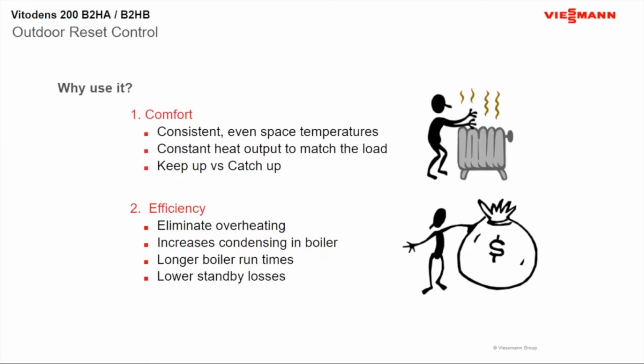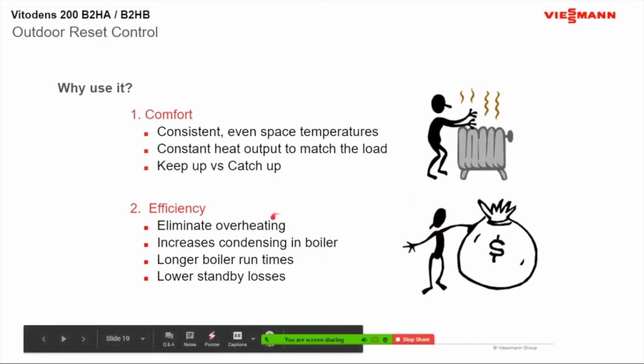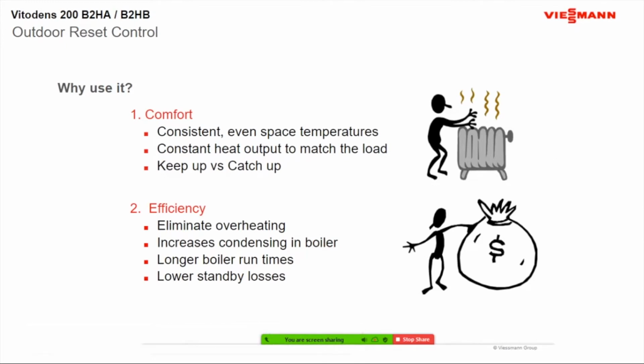So you're going to burn way more energy than if you just left that thermostat. I used to tell my customers, hey, once it turns 30 outside, leave your thermostats alone. Don't touch them. Because you're going to burn more fuel by trying to keep it down and then trying to raise it. All that energy you thought you saved by turning it down is just gone right out the window. It makes the boilers more efficient. Remember, we want the boilers to condense, so if we can run lower temperatures, we can get that boiler to condense. Longer run times, to me, give you a much more even temperature throughout and lower standby loss.